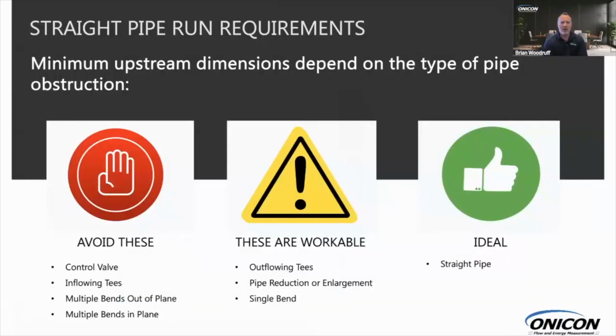All right, so talking about straight pipe run requirements. Definitely things that we try to avoid are modulating valves, inflowing tees, and multiple bends out of plane, because then it greatly increases that amount of straight run from that obstruction. It can be upwards of 30 or 40 pipe diameters. Things that are workable are outflowing tees, pipe reductions, and so forth. And then obviously it's ideal to have the longest amount of straight run.